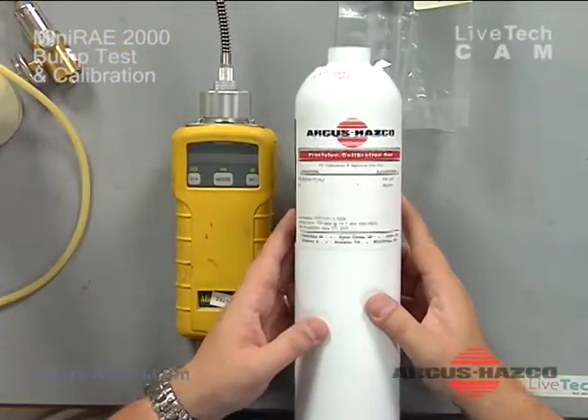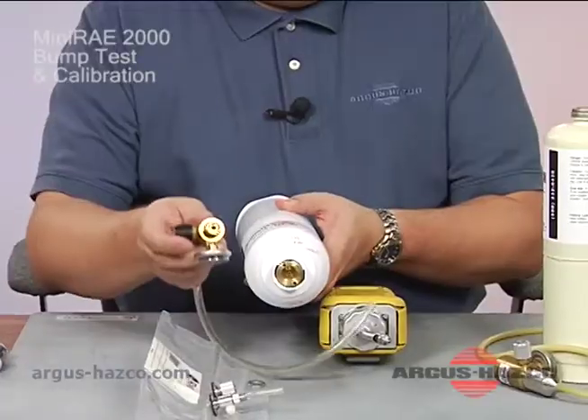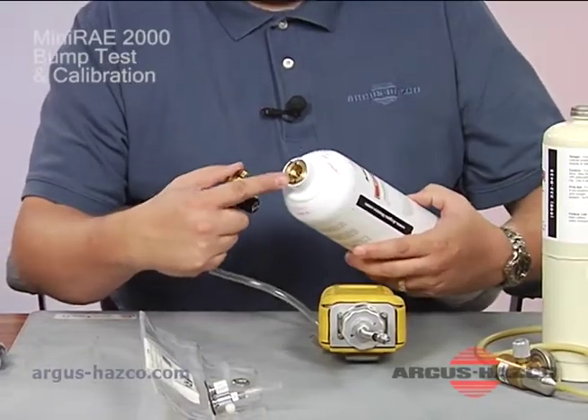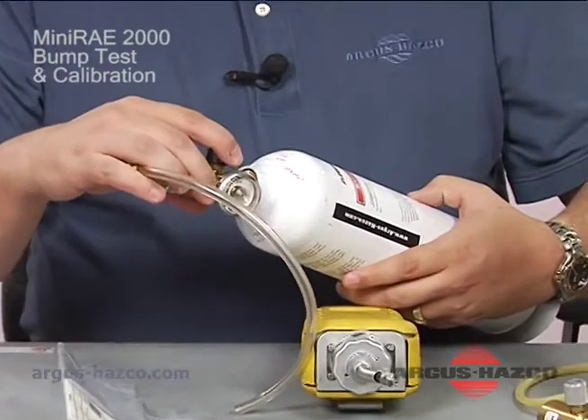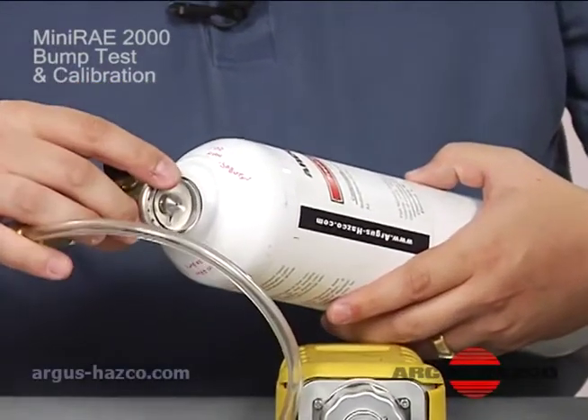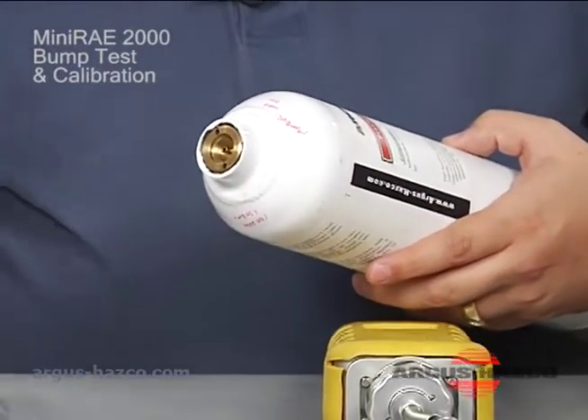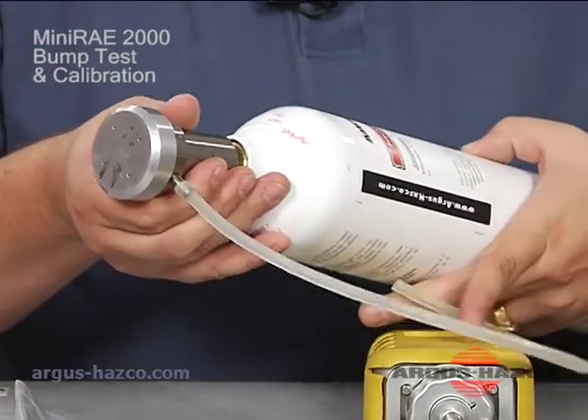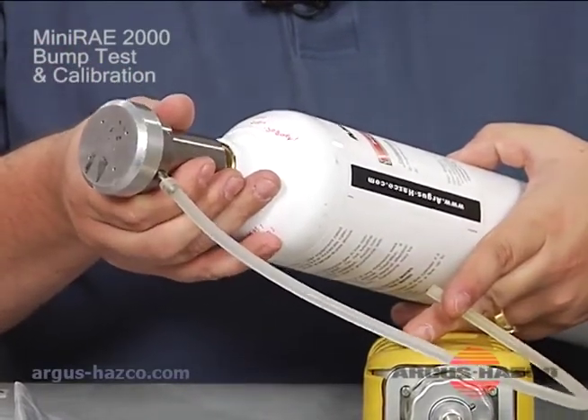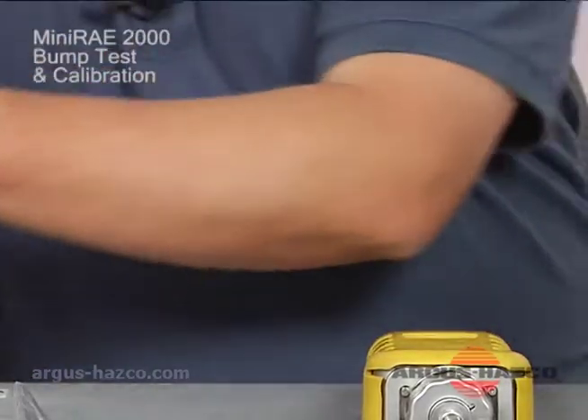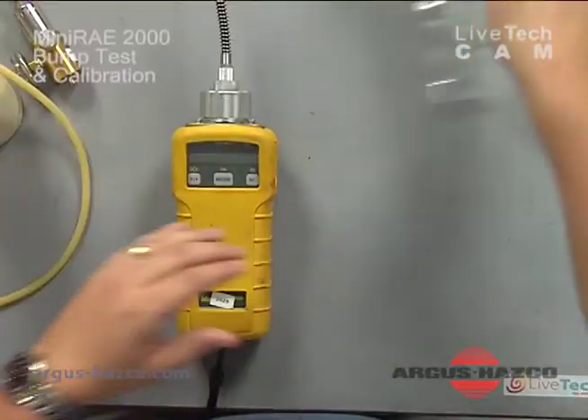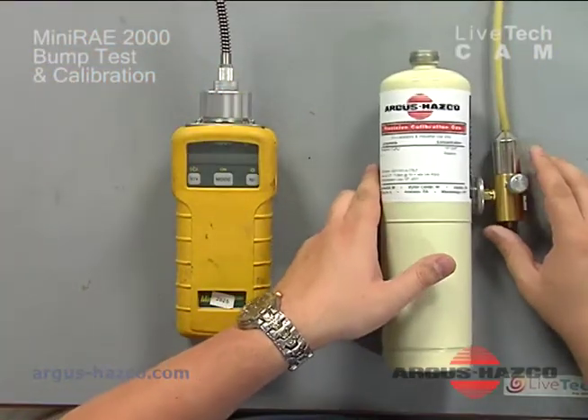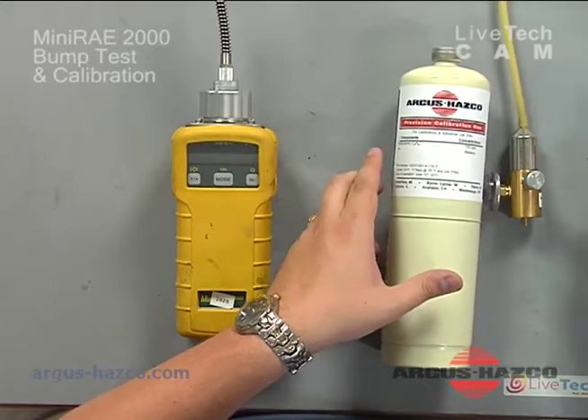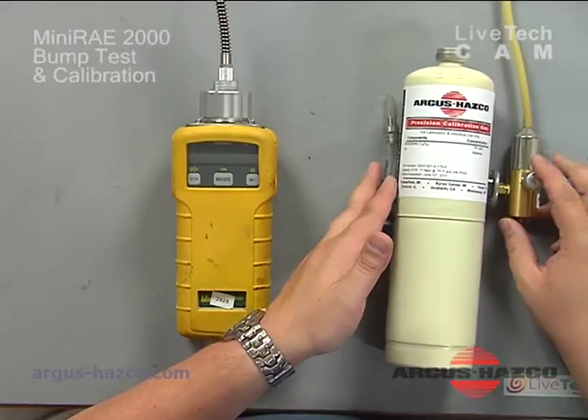Another cylinder is a 103 liter cylinder that would have your male fitting, female thread on the cylinder, that would have to screw on if you were to use this to fill your cal bag or to connect your demand flow regulator to hook directly up to your probe and let the pump pull the sample from the regulator. So in this scenario, we are using this cylinder of gas and regulator.